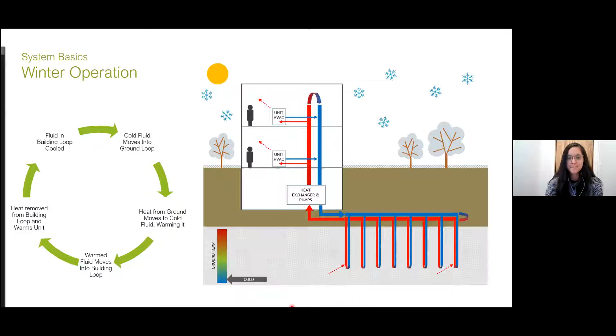Where that gets corrected is in the summer when the operation flips. So what we have happening in the summer is that the spaces are conditioned, so heat is taken out of the air within the unit and put into the fluid that then runs down into the building loop. That building loop fluid then goes and runs into the ground loop, where that heat then is put back into the ground. The loop temperature that goes back into the building is relatively cooler, and then that cycle can continue again.